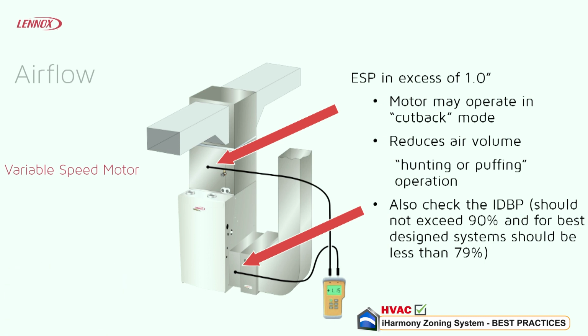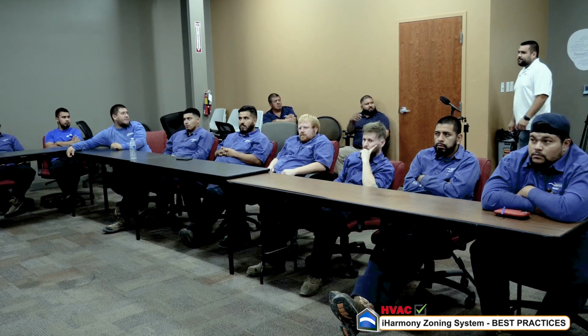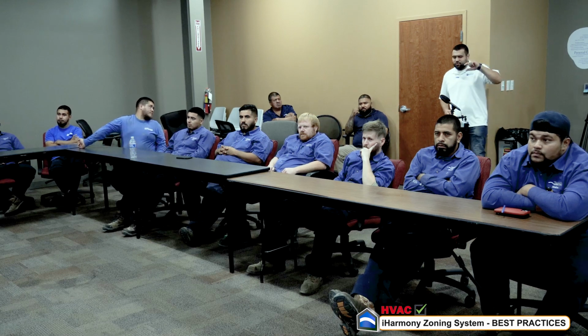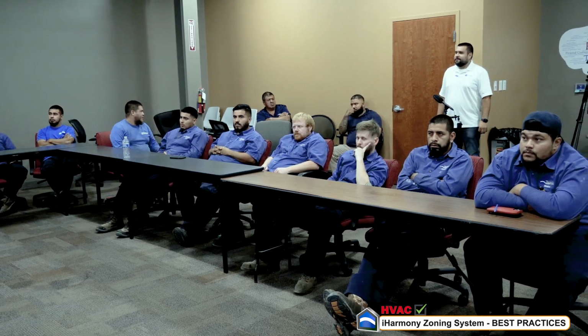The reason I'm asking is because we had, the job we did, the system kept turning on, and we came to the conclusion that it was... That scenario is very important. We touched on earlier about the zoning and being able to adjust each zone. That had a lot to do with that. If we have a small zone, we got to make sure we adjust the right CFM to that zone. Otherwise, it doesn't work right.